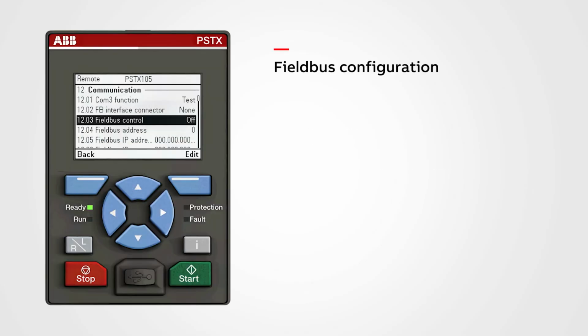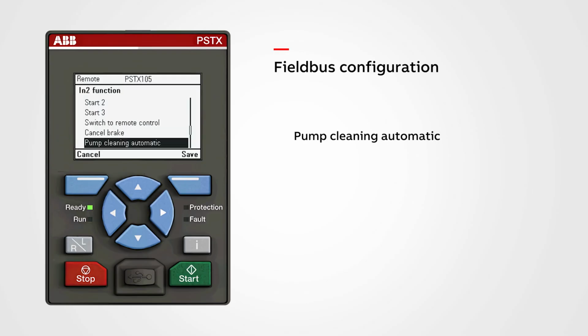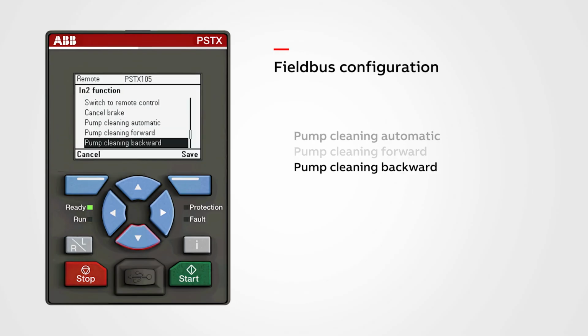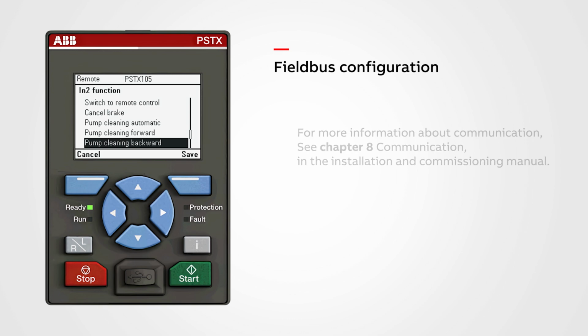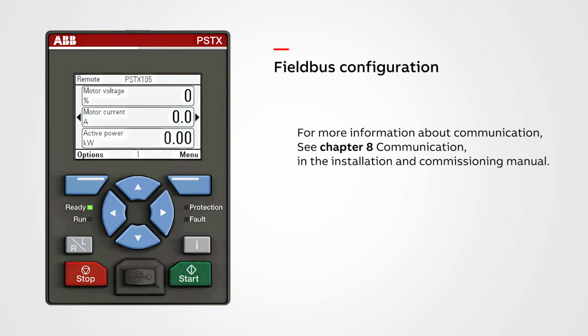Field bus configuration. Field bus digital outputs from PLC to soft starter can be used to run pump cleaning automatically, pump cleaning forward, or pump cleaning backward. For more information about communication, see Chapter 8, Communication, in the Installation and Commissioning Manual. We will cover field bus communication in another how-to.